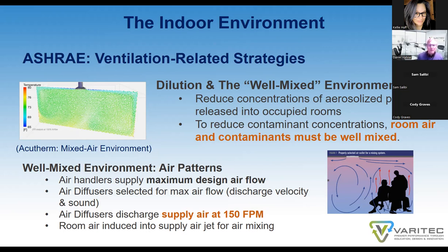So to reduce concentration of aerosolized pathogens and other contaminants released into a space, we need to make sure that the room air is stirred up and agitated so the contaminants are well mixed. We don't have pockets of high density or high concentrations of contaminants or infection that make a less healthy environment for the occupants. Well, how do we create a mixed air environment? Acknowledged by ASHRAE, air handlers supply air at a maximum flow rate during our peak summer design conditions. The HVAC system is designed to meet that air flow rate. Diffusers are selected for max flow, and a discharge velocity of about 150 feet per minute. By injecting air at high velocity, room air is induced into the supply air jet that results in mixing and hopefully uniform temperature throughout the cubic volume of space.